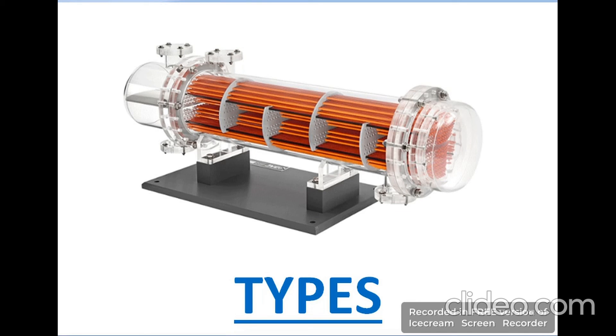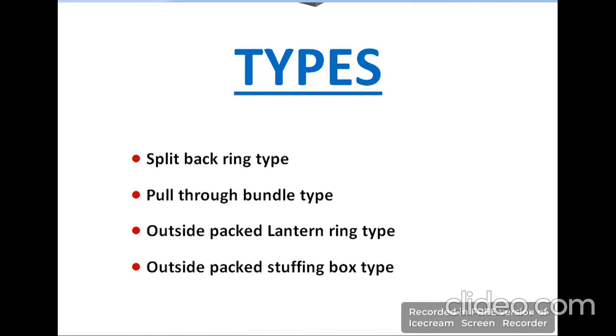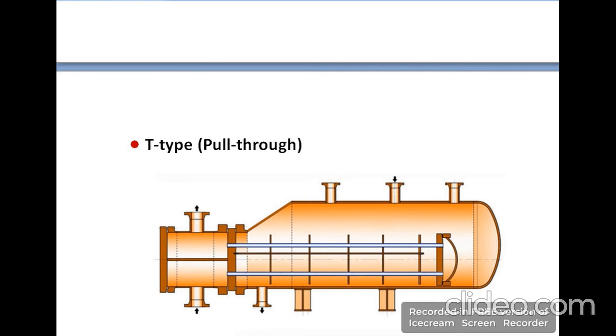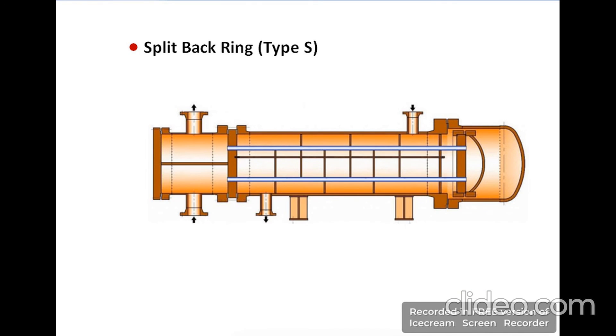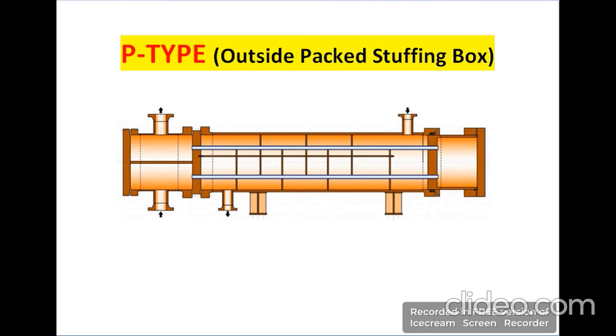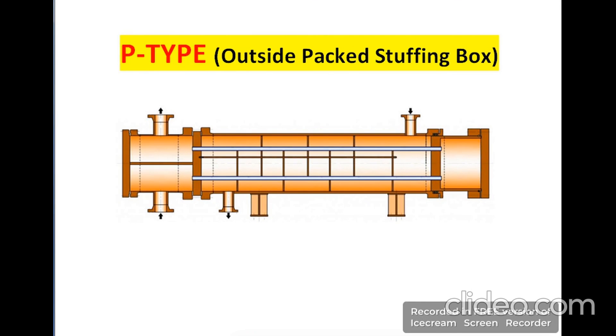Now the types of floating head heat exchangers are: first, the split back ring type; second, the pull through bundle type; third, the outside packed lantern ring type; and fourth, the outside packed stuffing box type. The pull through type is also called the T type due to its design. The split back ring type is also called the S type. The outside packed stuffing box type is also called the P type.